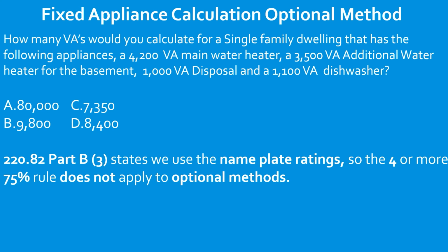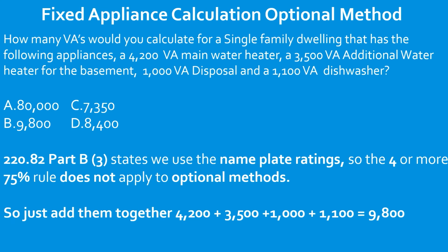220.82 Part B3 states that we use the nameplate rating, so the 4 or more 75% rule does not apply using the optional method. You're just going to total them all together, 9800 VAs, and you're going to select B.